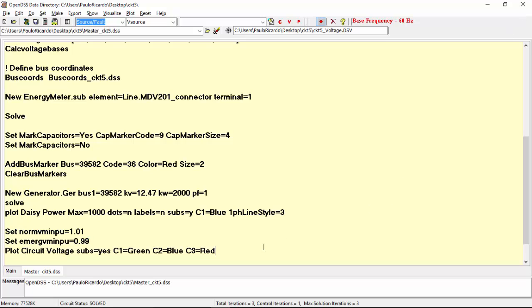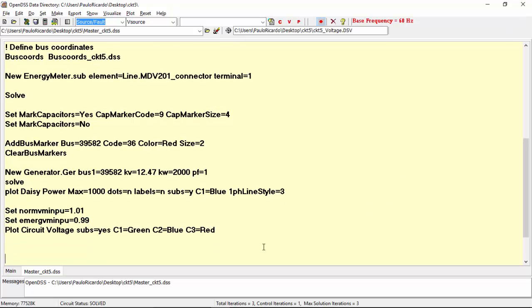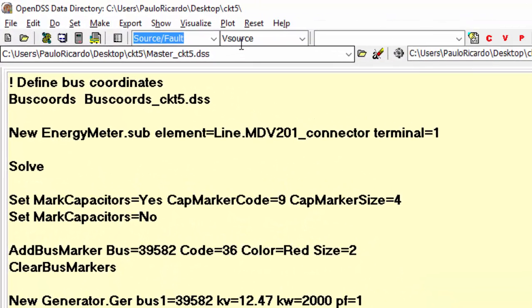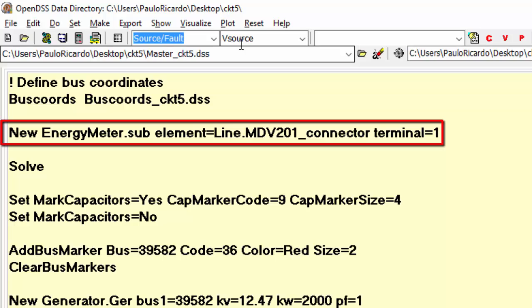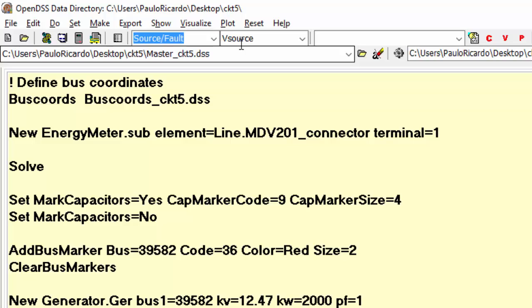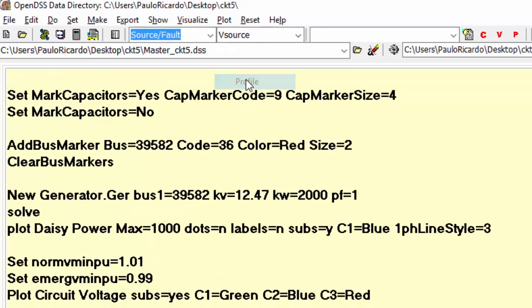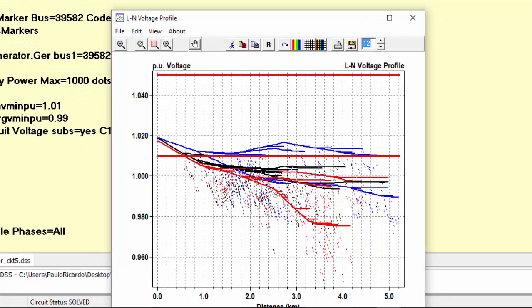Next plot we are going to explore is the profile. The profile is a plot that doesn't require bus coordinates. It's a graph containing the evolution of the voltage of the system versus the relative distance to the location of an energy meter element. The distance 0 is commonly considered as either the substation or the location of the circuit element. In the EPRI circuit 5 system, an energy meter has already been placed next to the substation. Then, all we need to do is to select the option profile in the plot menu. As you can see, it contains three profiles.